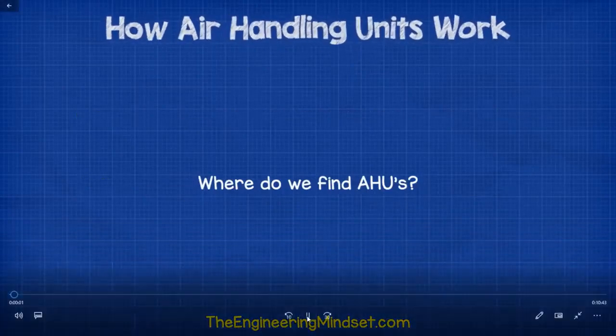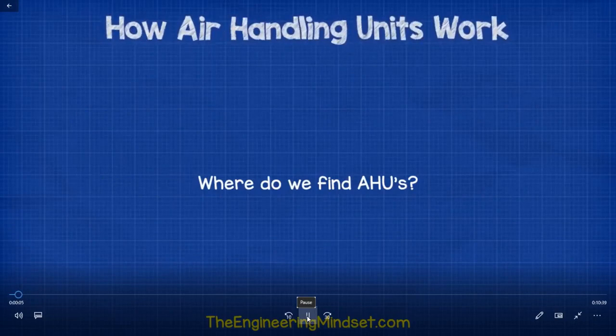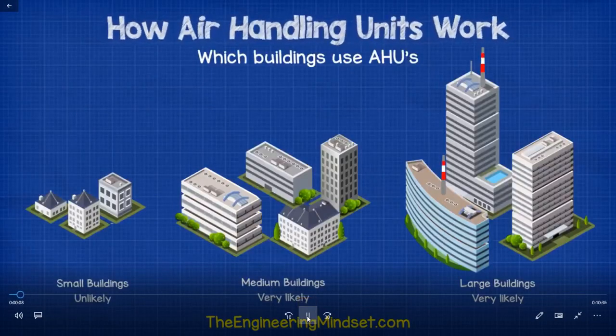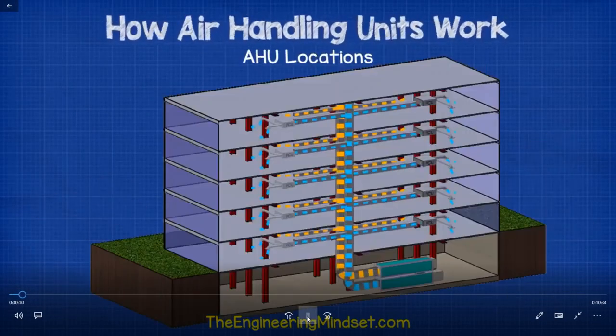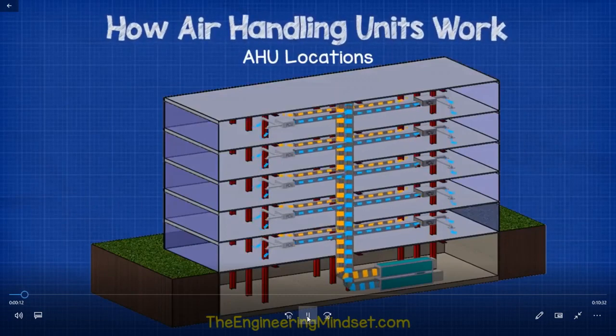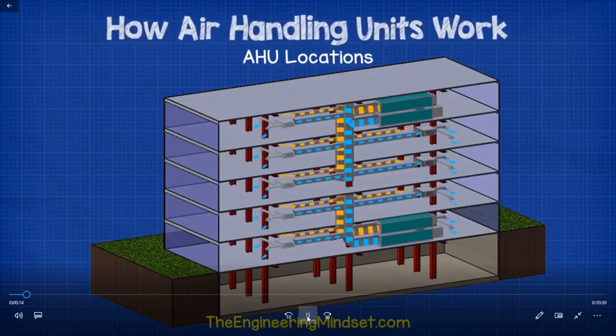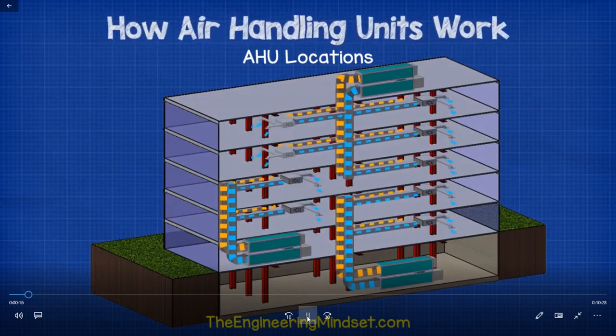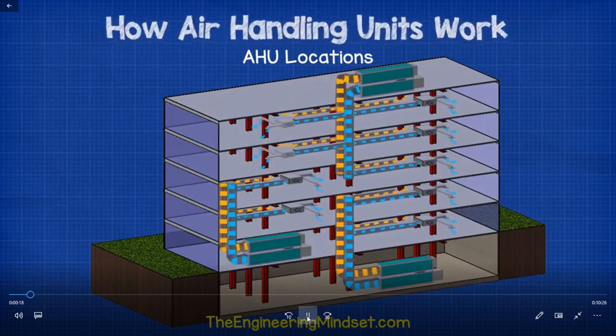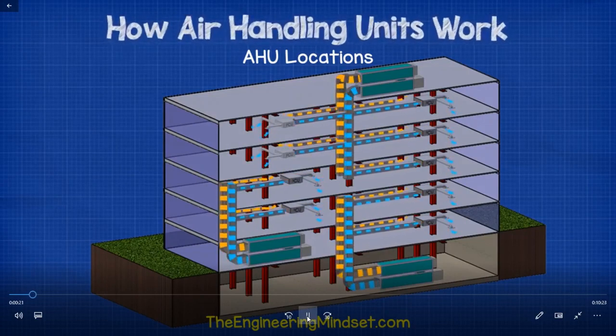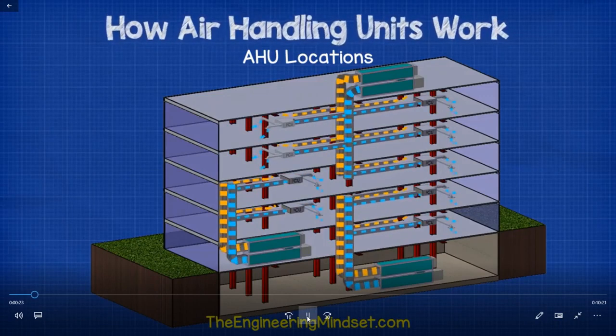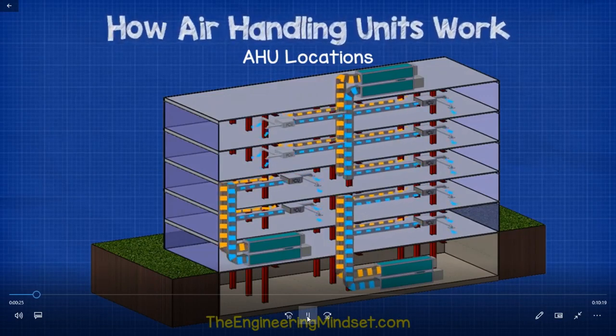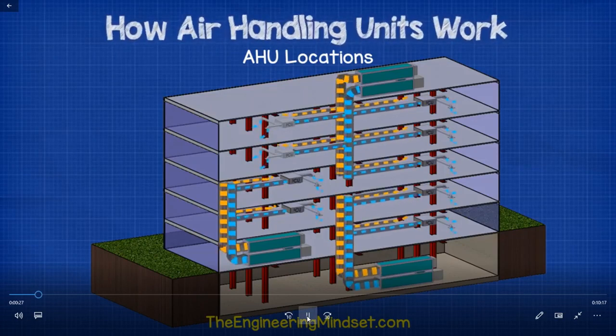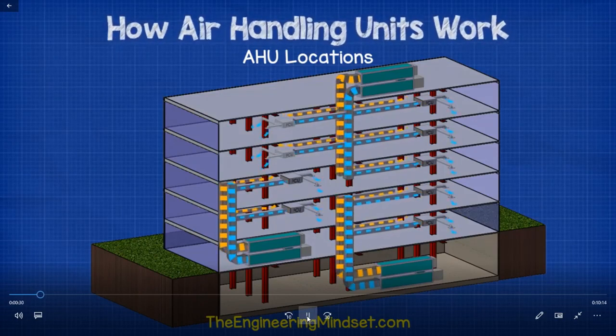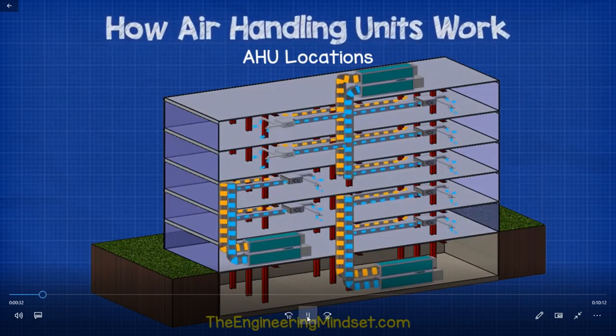So where do we find air handling units? Air handling units, which usually have the acronym AHU, are found in medium to large commercial and industrial buildings. They are usually located in the basement, on the roof, or on the floors of a building, and many large buildings will likely have a mixture of all of these. AHUs will serve a specified area or zone within a building, such as the east side or office areas from floors 1 to 10, or perhaps a single purpose such as just the building's toilets. Therefore, it's very common to find multiple AHUs around a building.